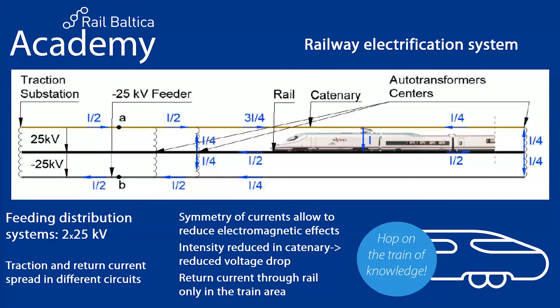If we zoom out on this part, for this 2 times 25 kilovolt system, for every substation we are now powering two electrical sections, with a separation section at the level of the substation and another one between. This system and the use of feeders allows us to feed electrical sections of the catenary that are longer, 25 to 45 kilometers. As a consequence, we can implement a substation only every 50 to 90 kilometers.